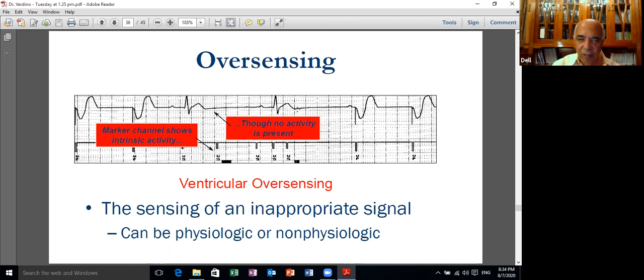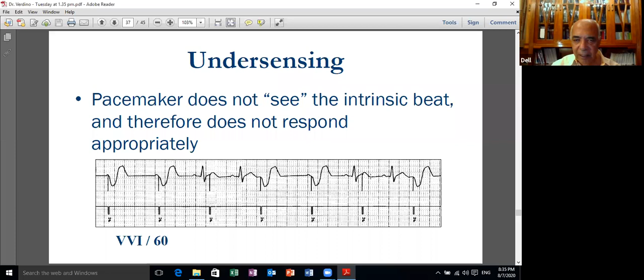Now again, the problem here can be in the can, in the lead, or in the contact between the lead and the ventricular myocardium. Undersensing: you get pacemaker spikes here where they should not be present. It didn't see this complex, so there is a spike delivered during the post-ventricular atrial refractory period. Again, it didn't see this spike, so this is undersensing.